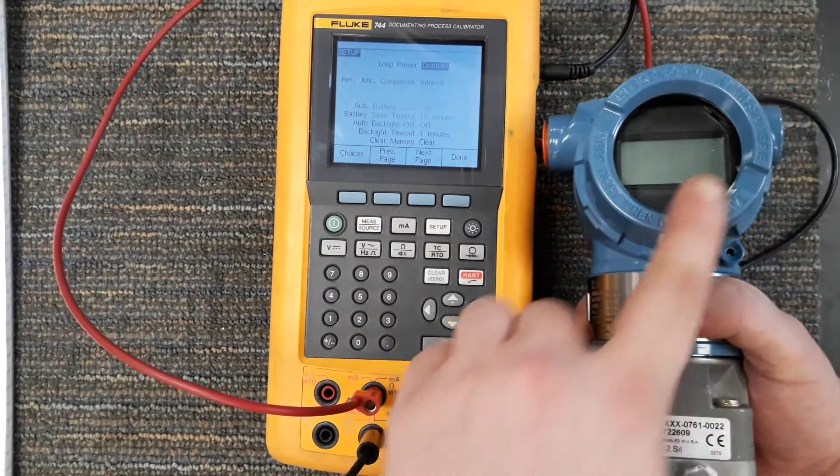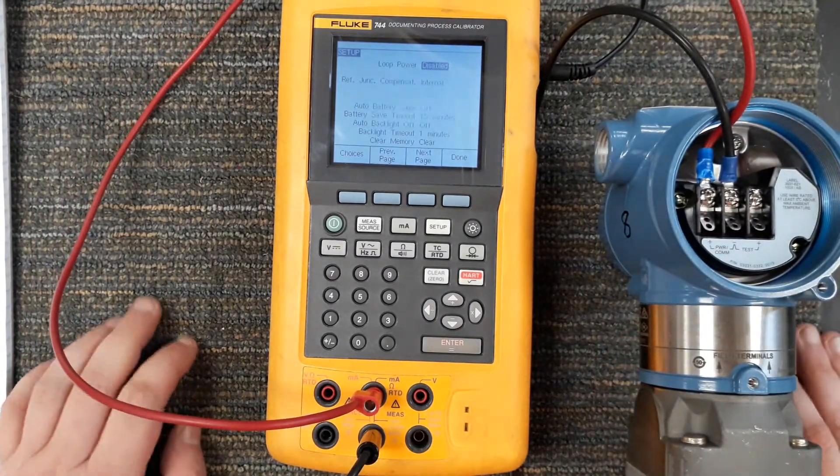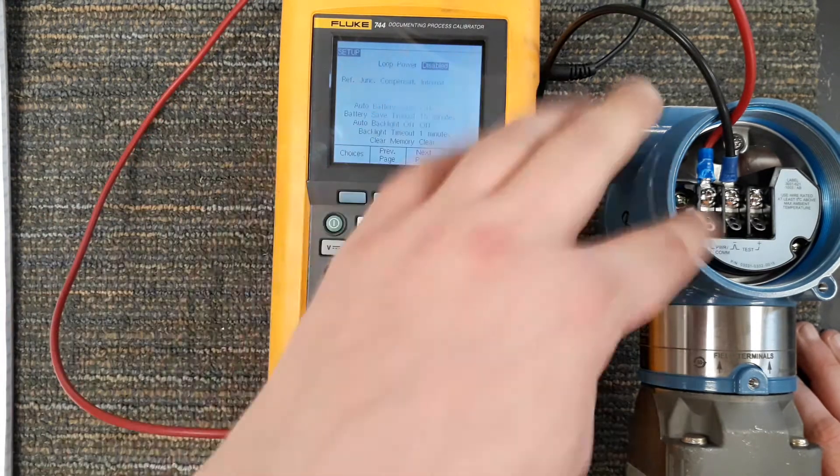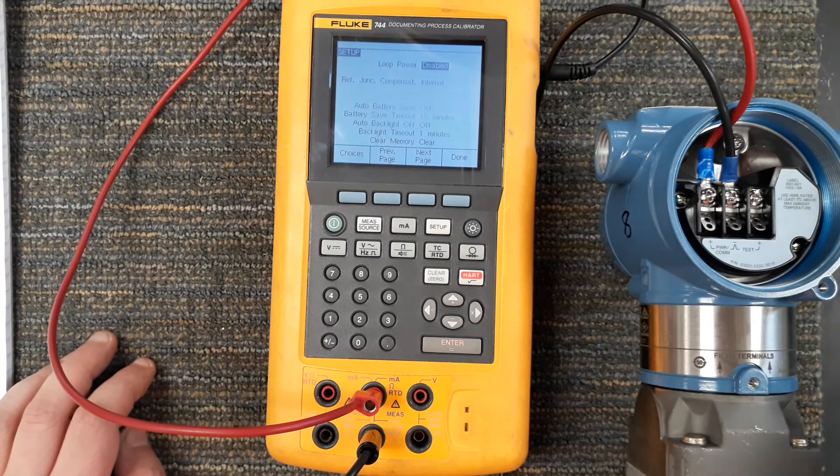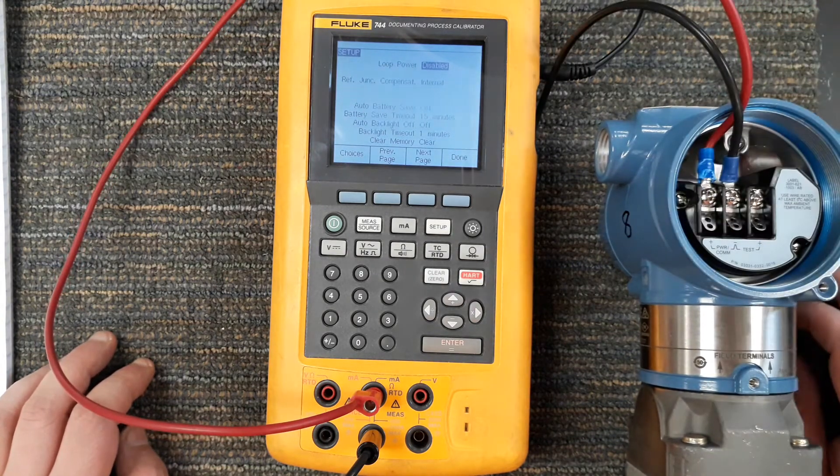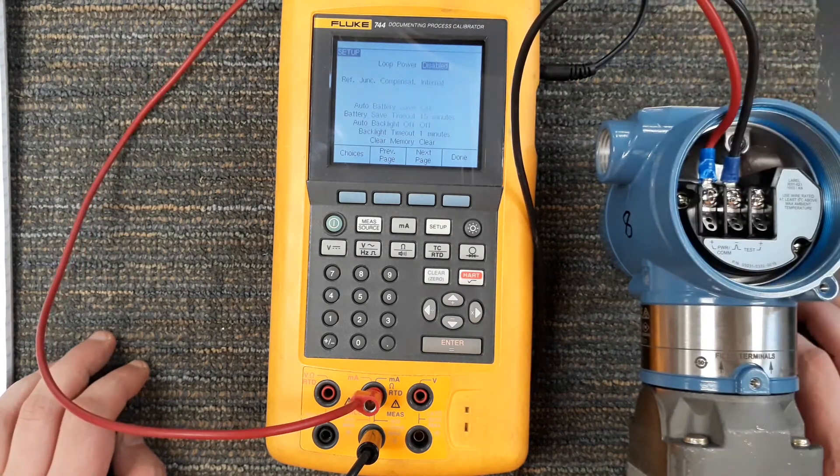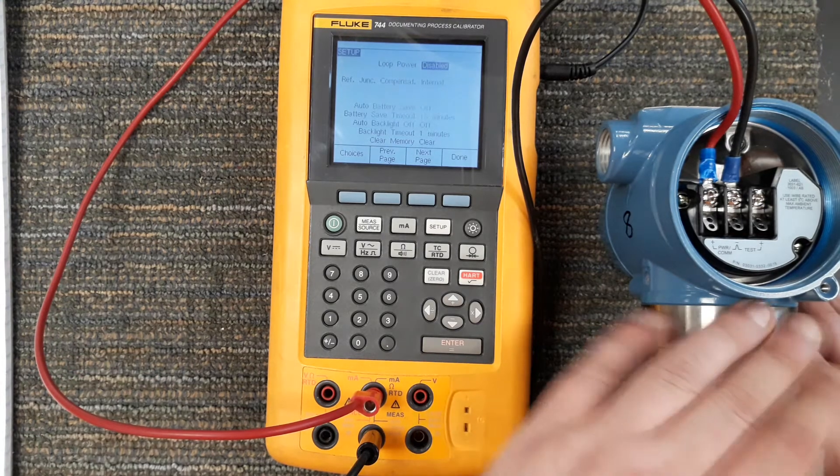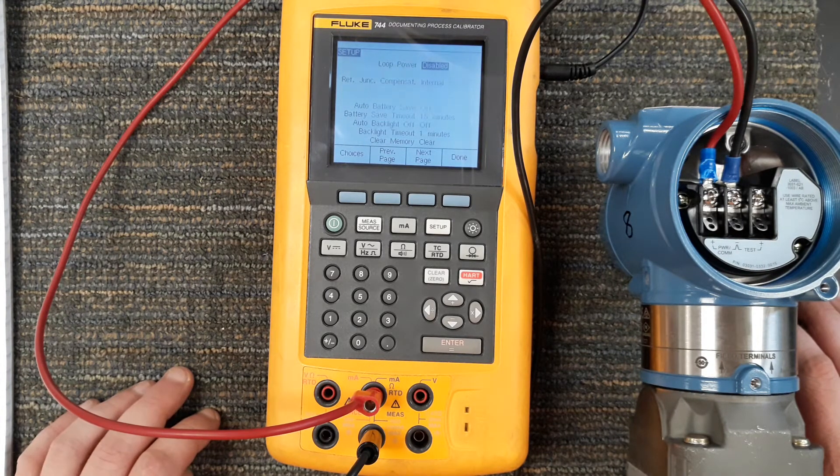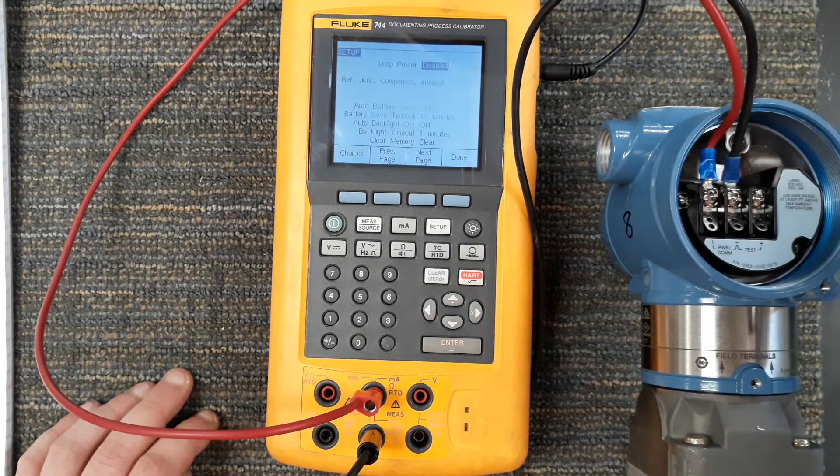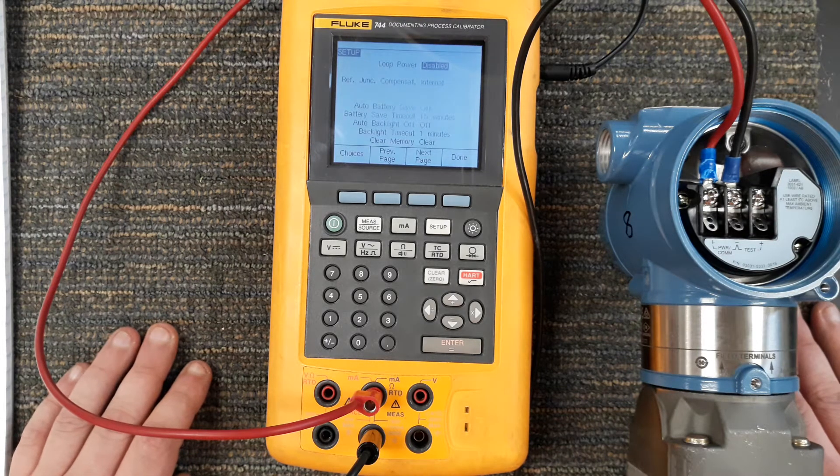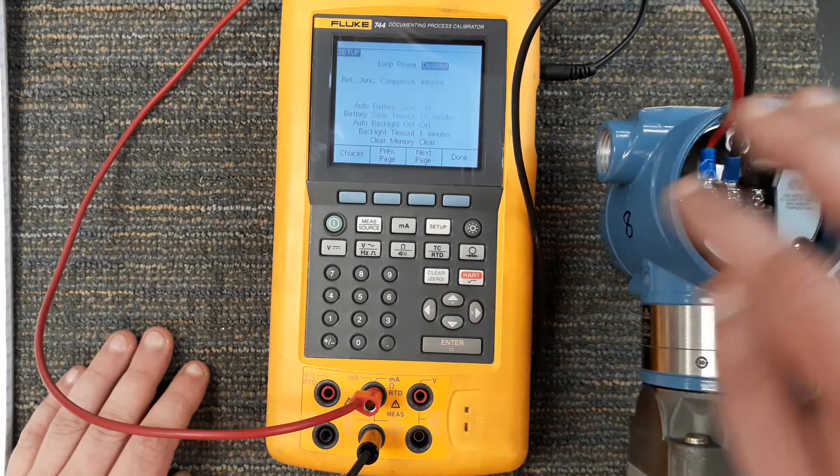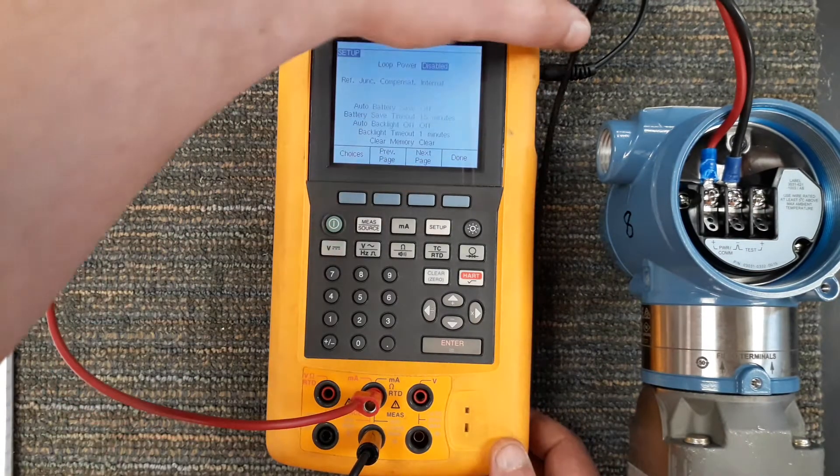It's very important that you do not enable the voltage before you hook up the wires. I highly discourage people to terminate or lift any wires that have potential voltage or power available to them. As you know with a lot of instrumentation this is out in the field and you could have vapors or gas clouds out there that are ignitable, and doing a termination or lifting can cause that spark that ignites that vapor cloud. So be very cautious, make sure that there's no power on the wires when you're lifting or terminating these wires. Just a good safety note for you.